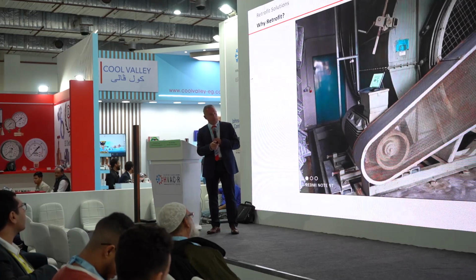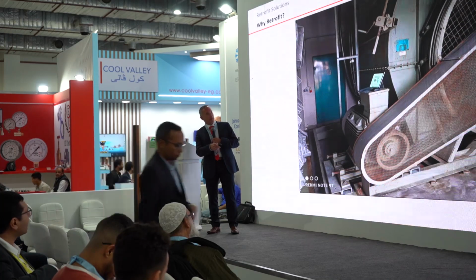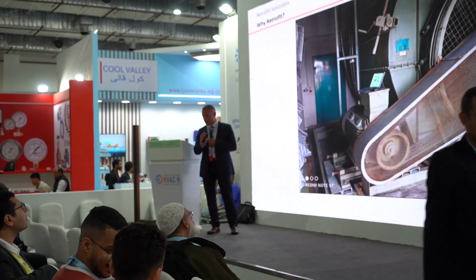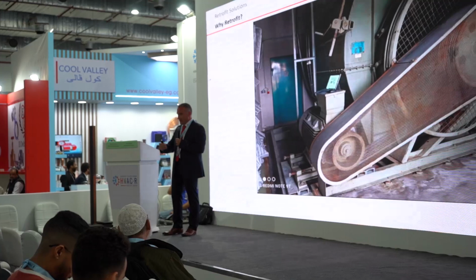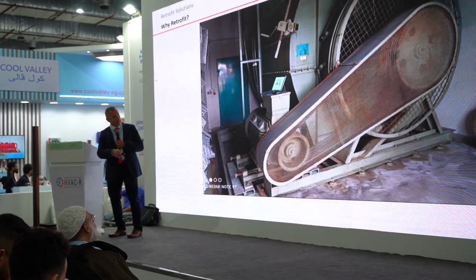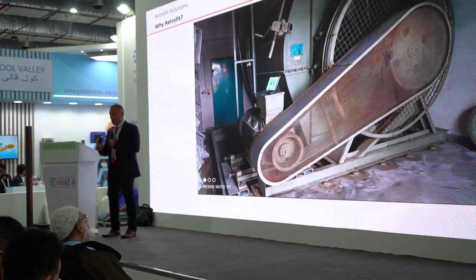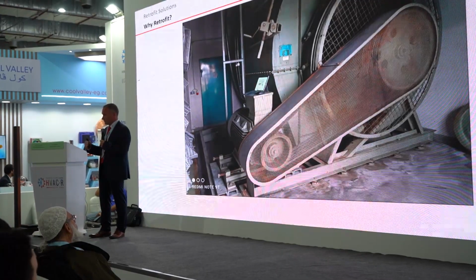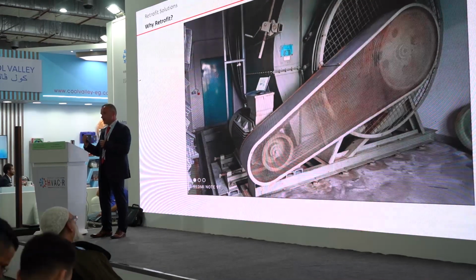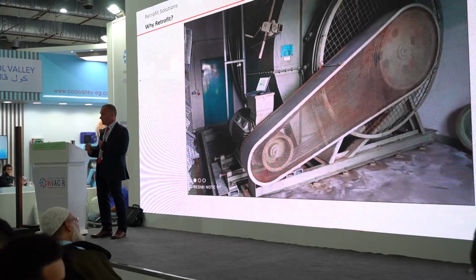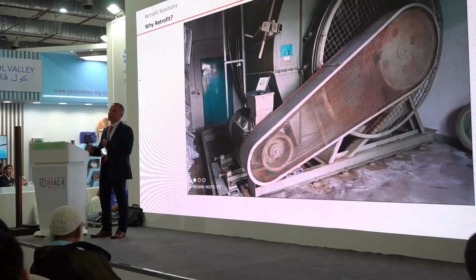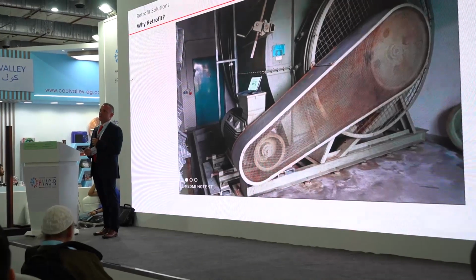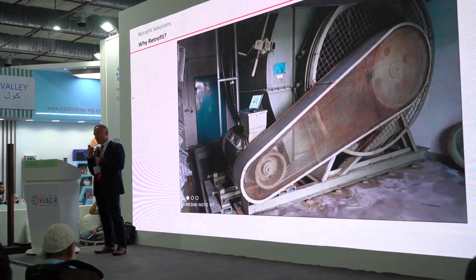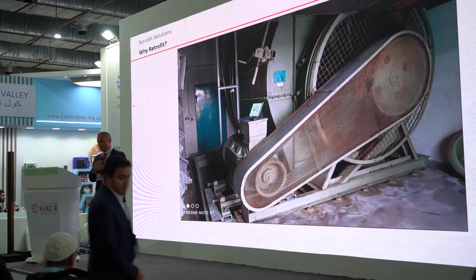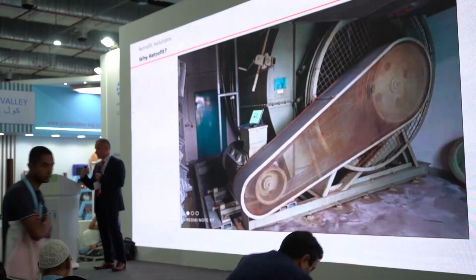One example here: you see this fence protecting the air inlet and also this big belt protection. All of this is disturbing the airflow. And disturbing the airflow means that you need higher pressure, higher volume, more energy, and this all creates a high energy consumption. So we are looking for customers which are running such fans and replace it by an EC fan grid.